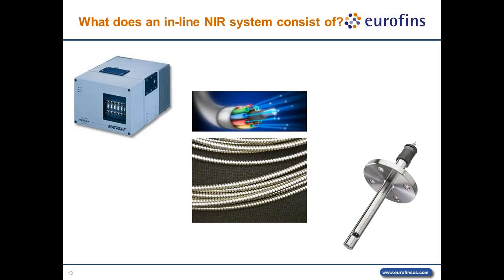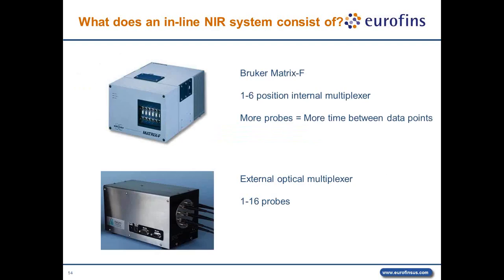So what does an inline NIR system consist of? An inline NIR system consists of three main components. The first and most obvious is the NIR spectrometer with fiber optic capabilities. The second would be a set of fiber optic cables that run to and from the instrument and probe. The third component, being the probe itself, would be installed in the plant or production area. The NIR instrument provides our signal, our detector, and the ability to interface with a single or multiple fiber optic probes.